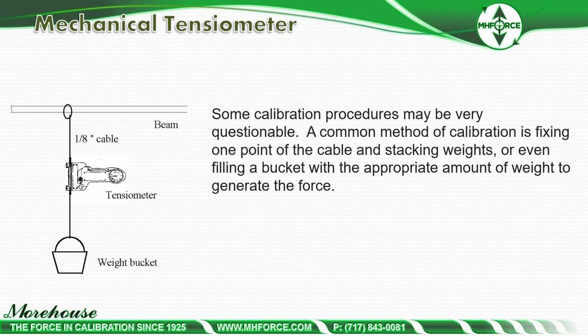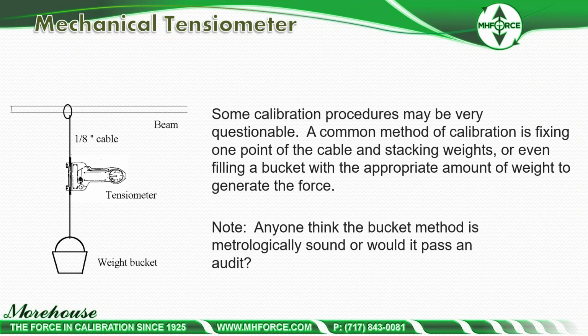I think it's certainly more acceptable than using a torque stand, because if you use a torque stand, remember, torque is force times length. So in that, you're going to have to backtrack a bunch of calculations that never make sense. You're going to have a rigid cable. You're going to be doing it at some kind of vertical plane where a lot of error could just happen. I am not a fan of using a torque system to calibrate tensiometers. You're asking for problems. You're asking for errors. This is not the greatest either.